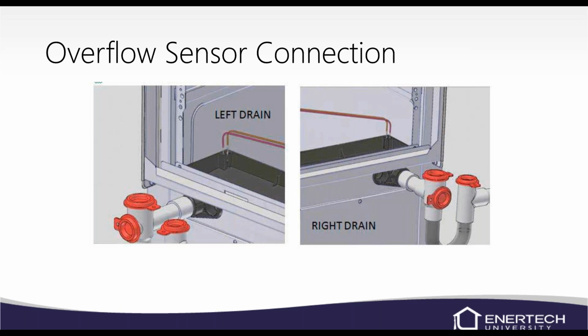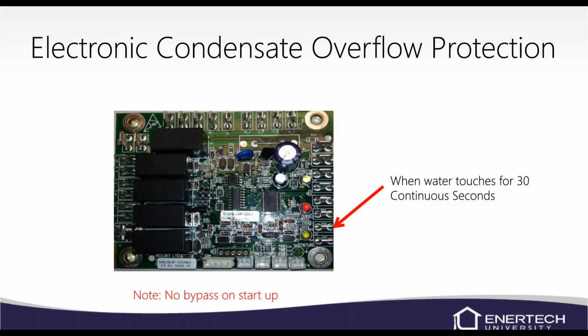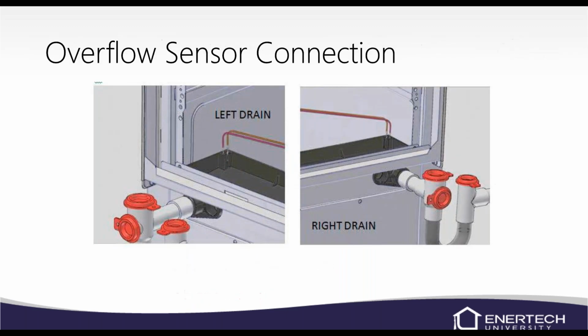But basically, there's two wires that run from this lockout board. There's a purple, I think a brown wire or something. And so basically, the water completes the circuit and sends a signal to ground, which in turn locks the unit out. If you ever have a condensate overflow lockout and there's no water in the pan, make sure you have a trap on the unit, because our units won't drain properly without a trap.